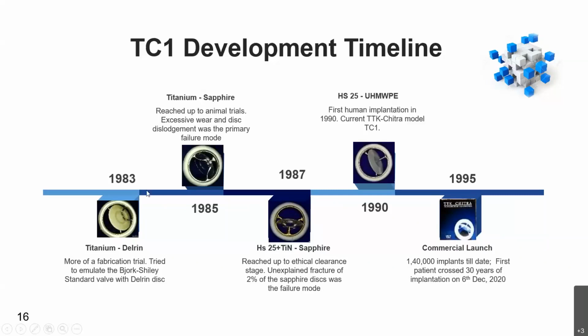Then the disc, from Delrin, we had already moved to a single crystal sapphire. The same single crystal sapphire prevailed in the case of the third model. But to our surprise, about 2% of the sapphire discs fractured in our test systems. And actually, we didn't have sufficient quality control strategies to screen out this 2% of sapphire discs. And because of this particular reason, even though this was a good valve and would have lasted about 15 to 20 years without any problem in the patient, we had to abandon this particular model. Then the search for an alternative material for sapphire was started, and it took about another 3 years to come out with the currently available TTK Chitra valve.